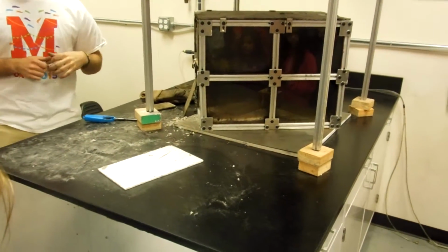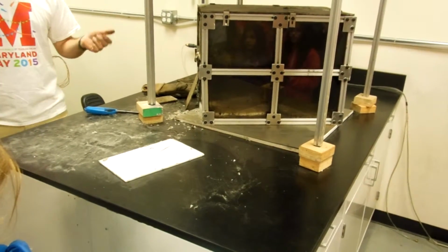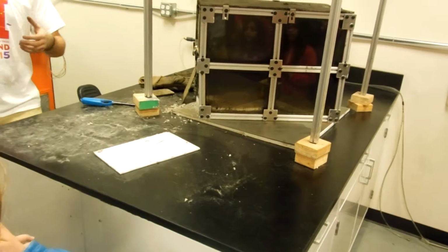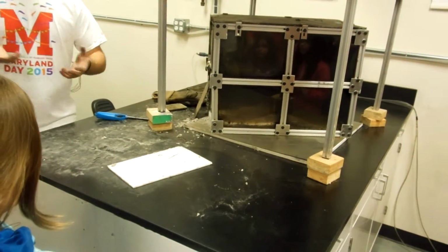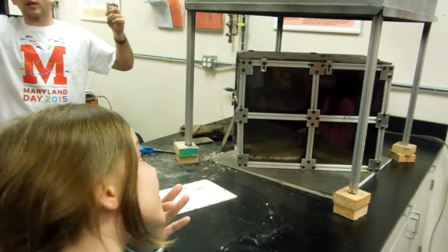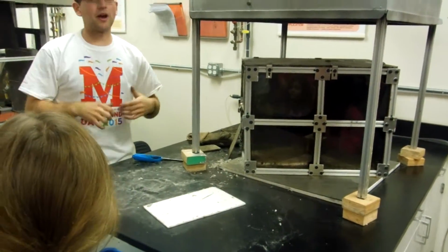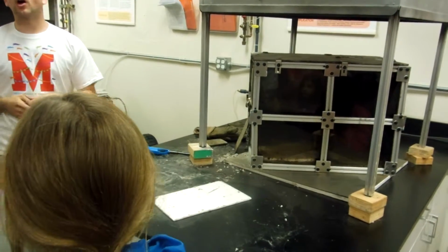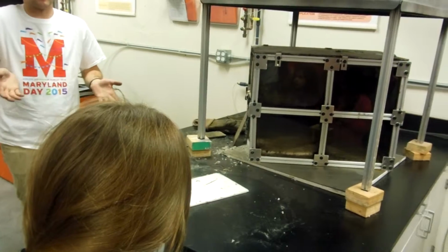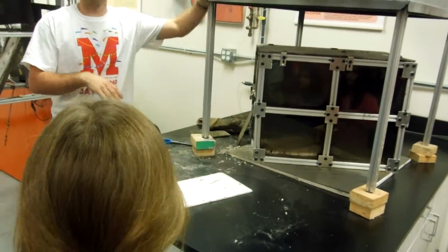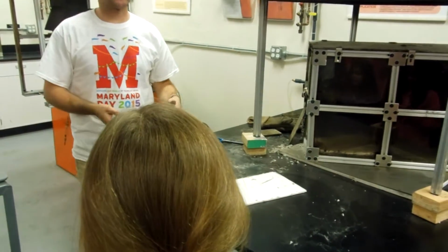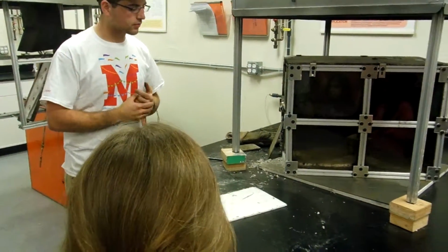So, a lot of times if you know what fire protection is, people think, oh, you guys design sprinklers, and that is one thing that we do. That is one thing of multiple things that we do. For this room in particular, an engineer had to think, all right, I have to put sprinklers in here, but what type of sprinklers do I need to put in this room? How far apart do they need to be spaced? We have to think about what materials are going to be in here that are going to burn. I mean, how flammable is the stuff in this room? I know that all these components are metal, they're not really going to burn, but we're going to house chemicals in here that are flammable. You have to take that into consideration.